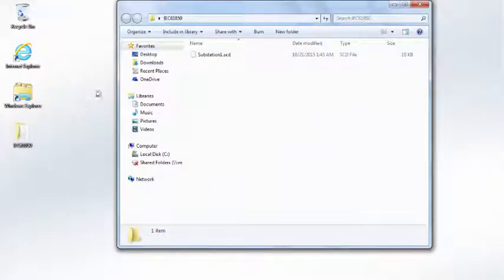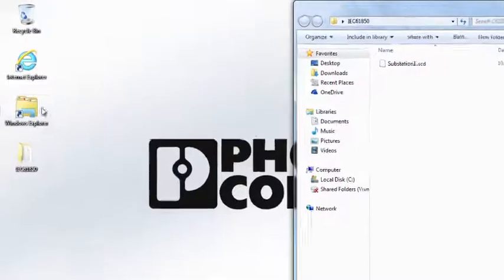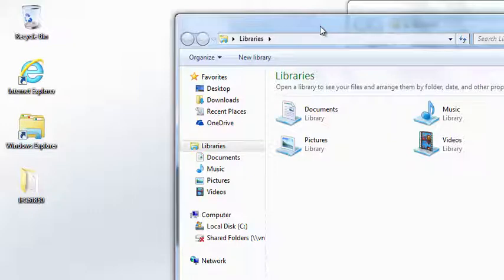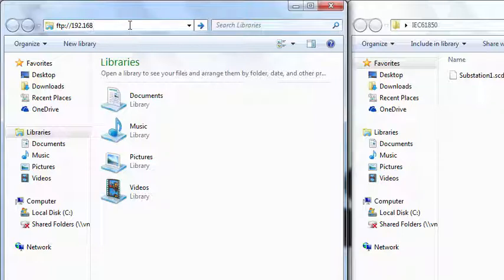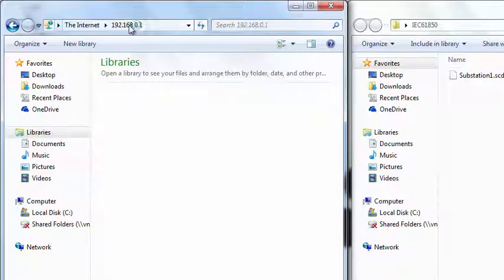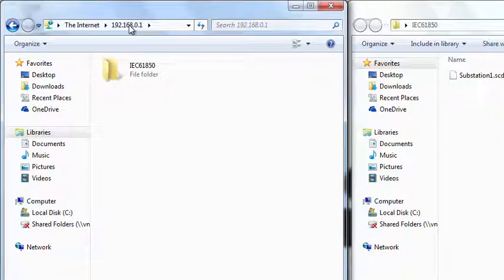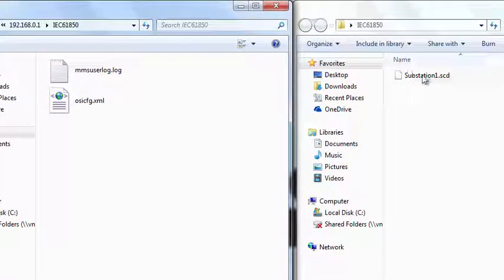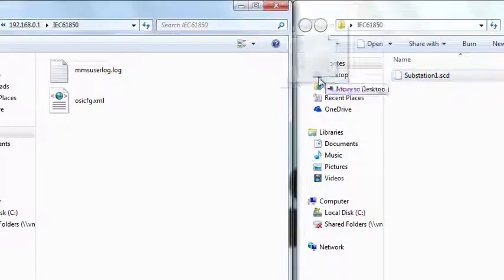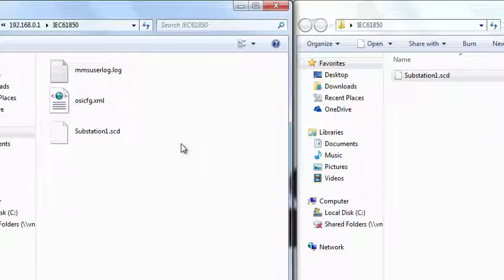Use the file explorer to access the file system of the bus coupler. Enter the FTP address — composed of the abbreviation FTP and the IP address of the bus coupler — in the address line. This gives access to the root directory of the bus coupler and, with a double click, the directory IEC 61850. The required configuration file is located in the already opened project directory and is transferred via FTP by drag and drop to the file system of the bus coupler.